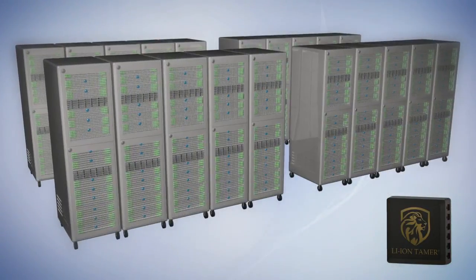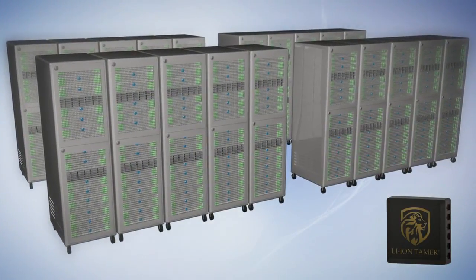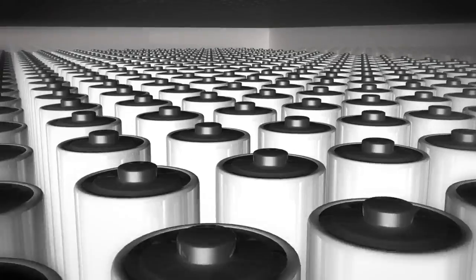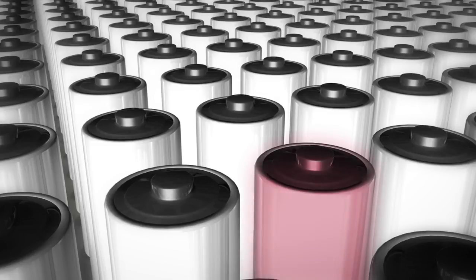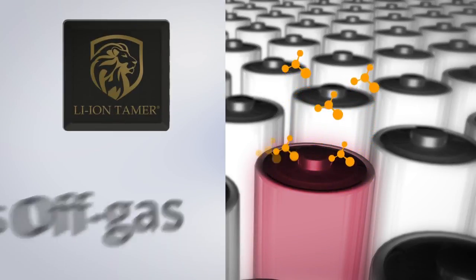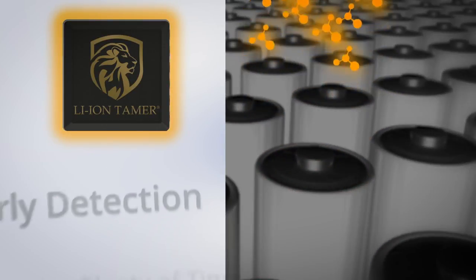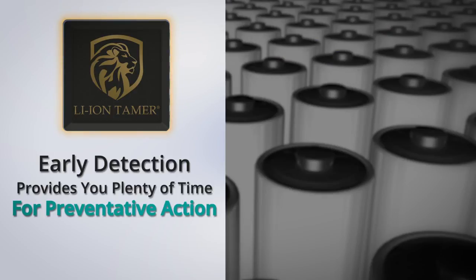An off-gas monitor is placed at each battery rack to monitor off-gas events. It can detect a single-cell battery failure in a typical open-air battery rack. When failing lithium-ion batteries emit off-gas, Li-ion Tamer can detect this precursor before the cell fails. Now there's time to take preventative action.